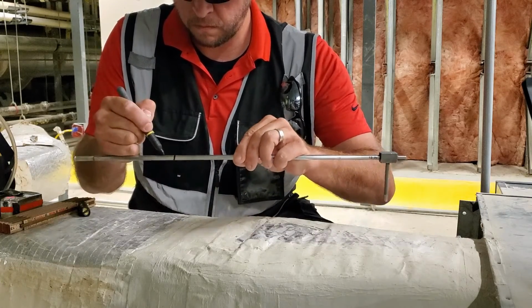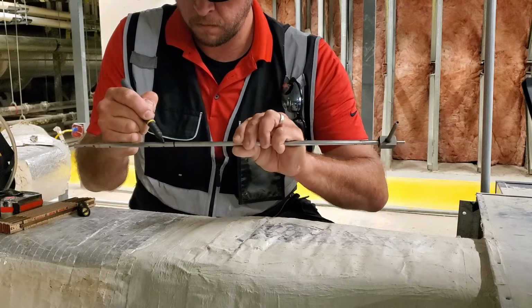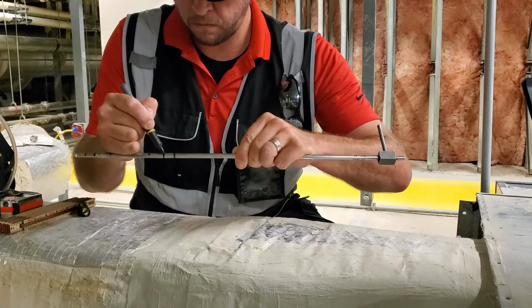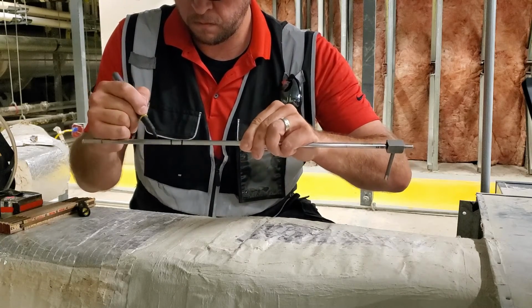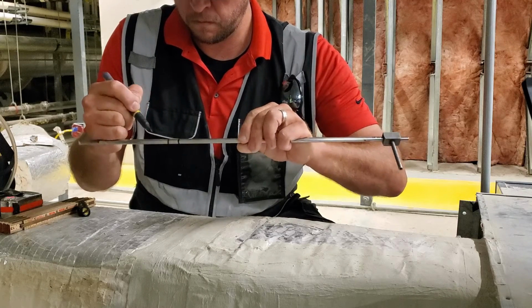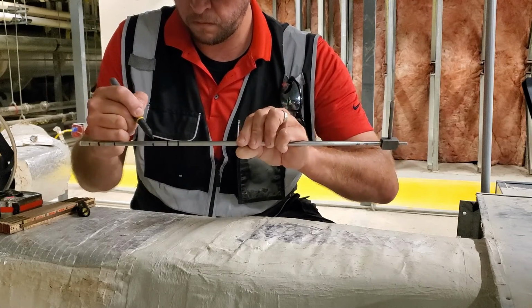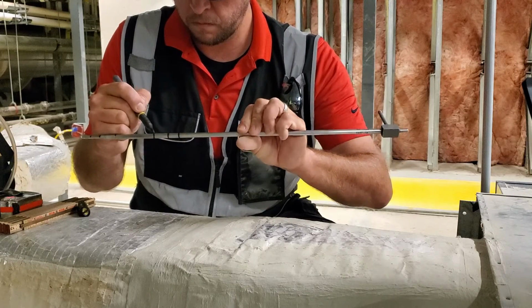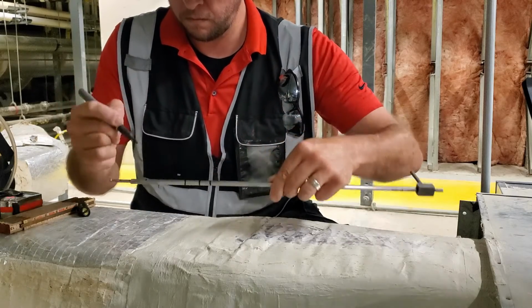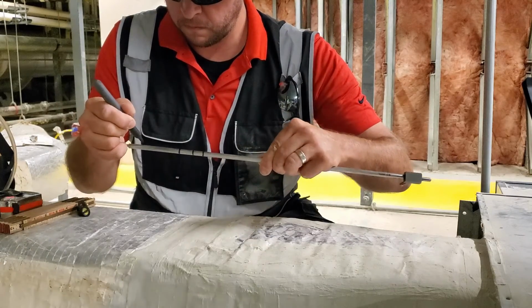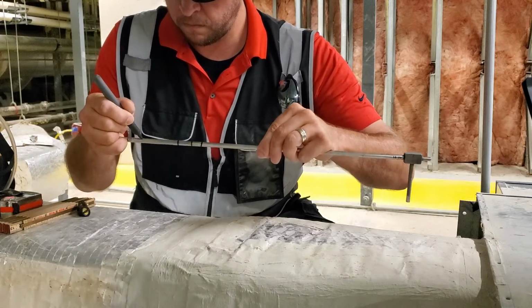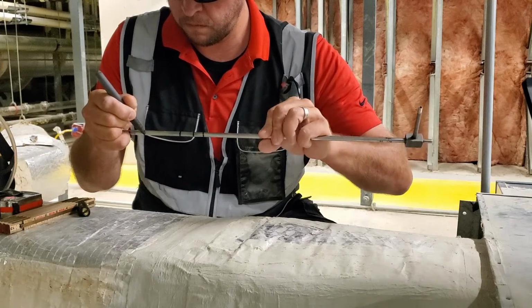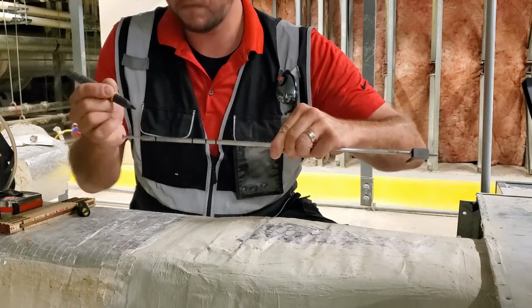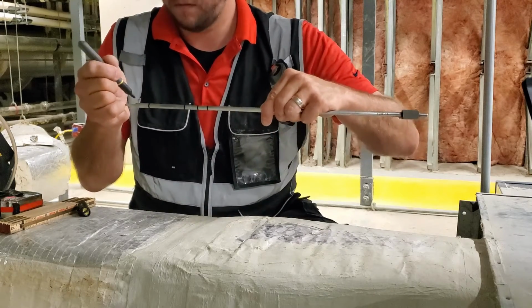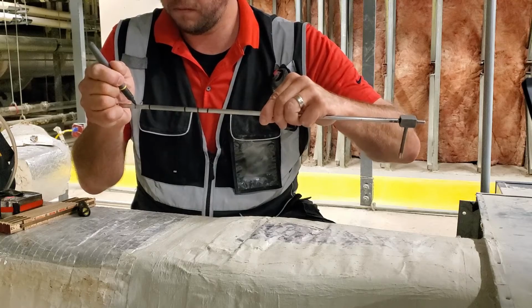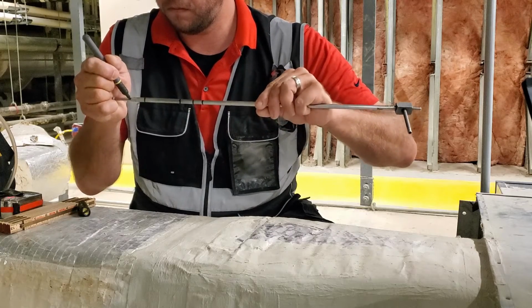And you know, some people like to tape their airfoils. We just like to use a marker, and then we get a scrubby to scrub those off for other duct sizes that we will traverse in the future. So like I said, you definitely don't have to traverse the terminal unit. You can measure the associated grills with the flow hood. Just make sure you grab a correction factor for each grill type that you measure, just to make sure it's going to be as accurate as possible.